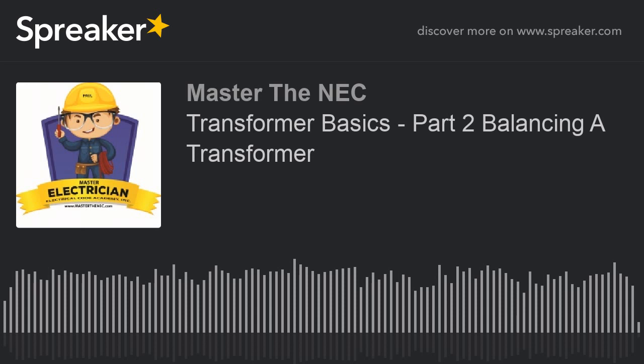So now let's do that. So I have 4 kVA. I'm going to put 4 kVA in phase A. That takes me up to 24 on phase A. And since I already had 26 on B, I'm going to leave it alone. And I'm going to put 4 on C. Remember, we have 3 of them. So now it brings that one up to 24. Both of those are still less than B, which is at 26.